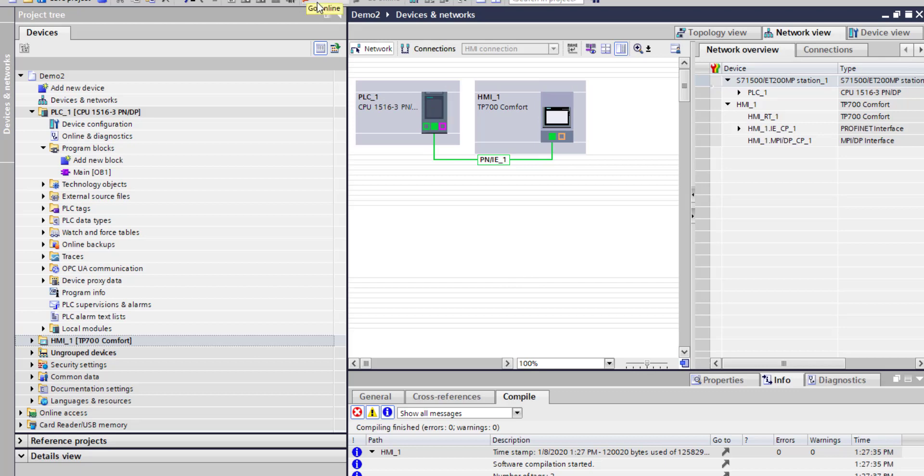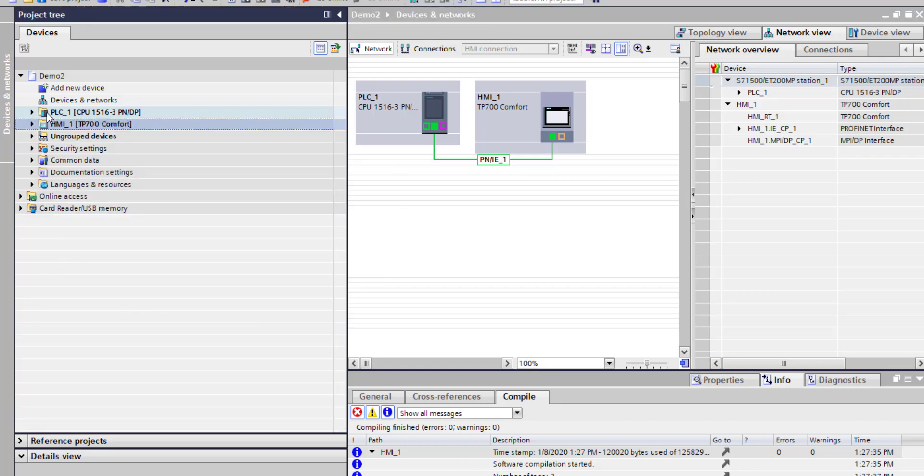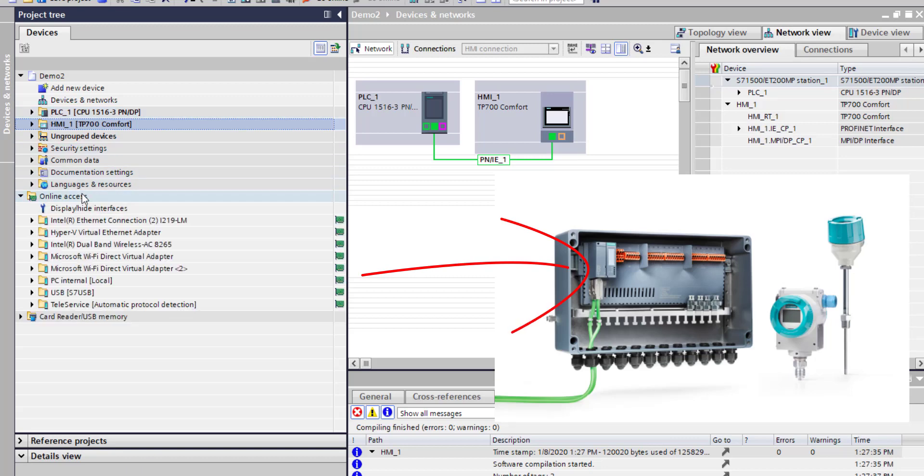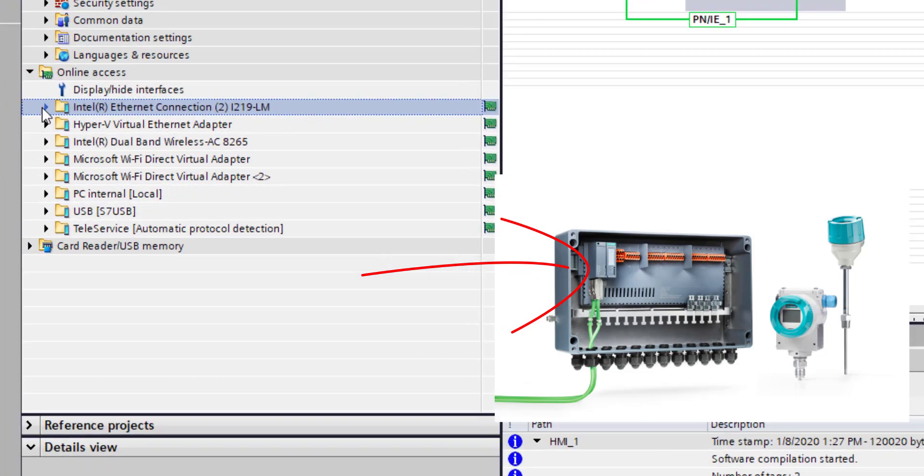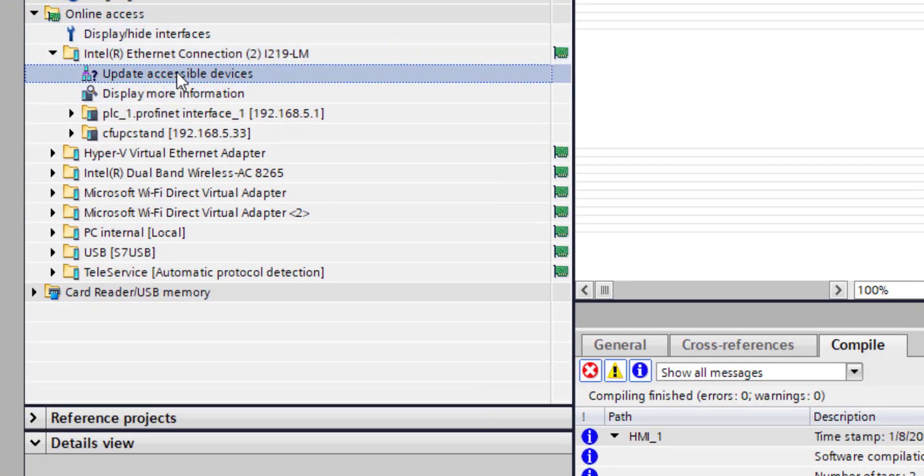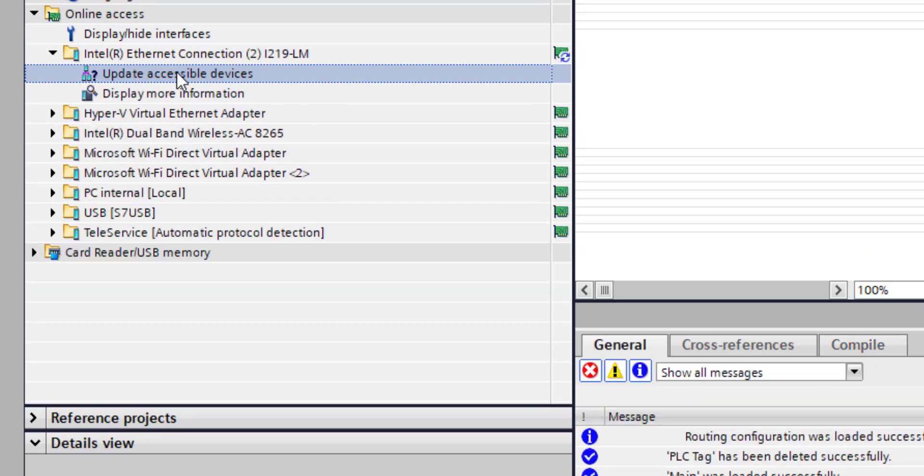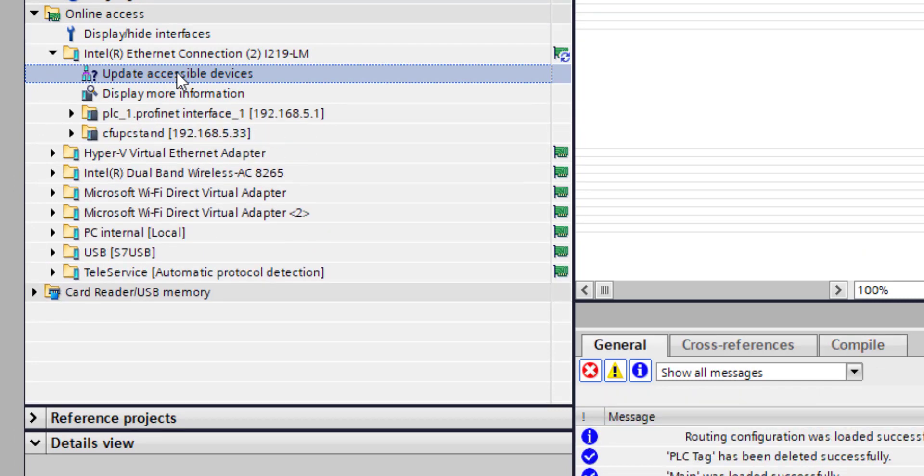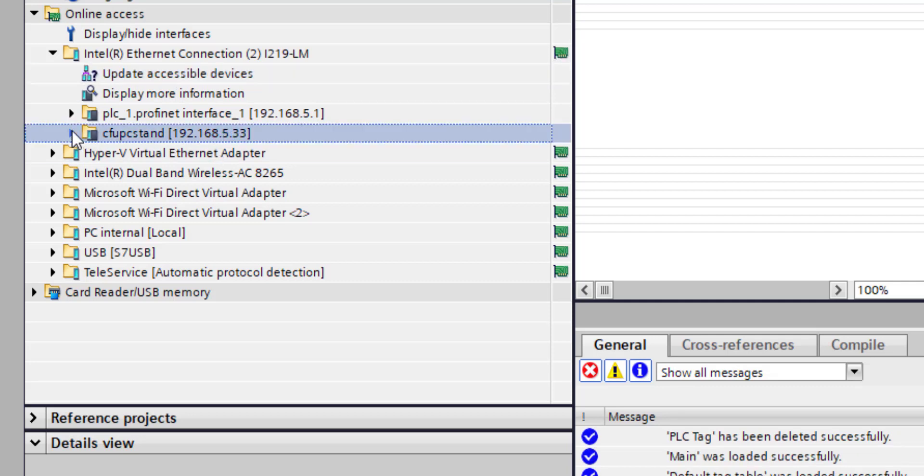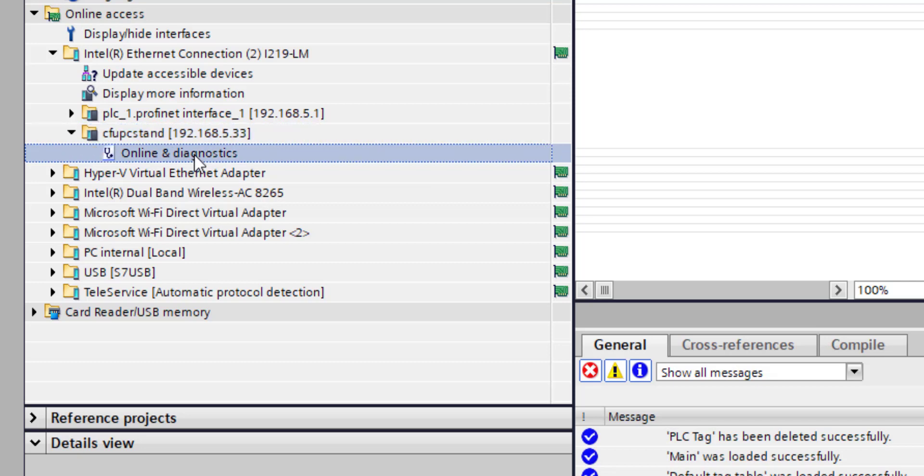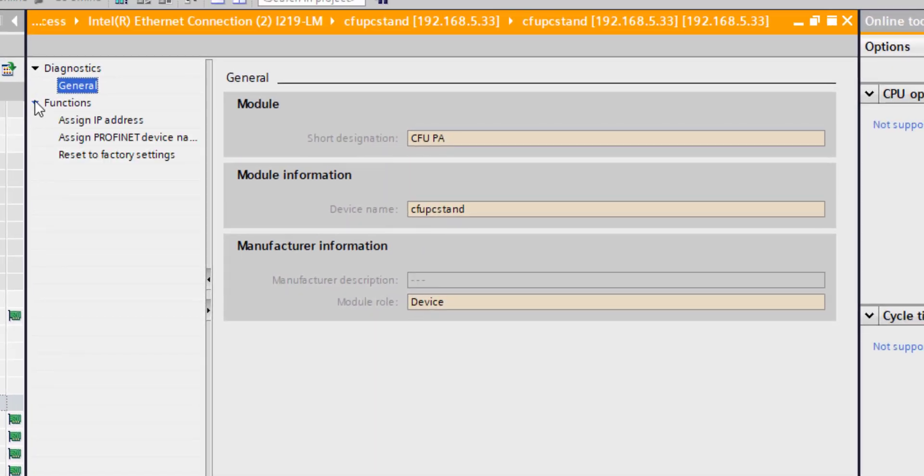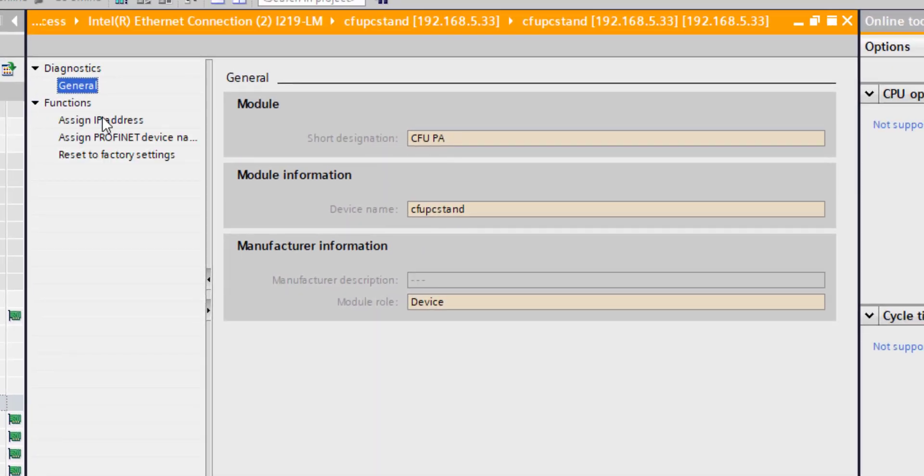I have my HMI added to the project - just make sure I'm offline. The next thing I need to do is add my Compact Field Unit, which is my PROFINET to PROFIBUS PA. Now if you're not sure of the IP address, because obviously the Compact Field Unit has no display, you need to know what IP address it is. You can use Primary Setup Tool, but you can also use online diagnostics. If I just update my devices, it will scan what is connected to this network. I can see there's my Compact Field Unit with my IP address.